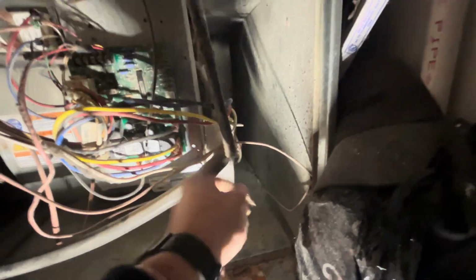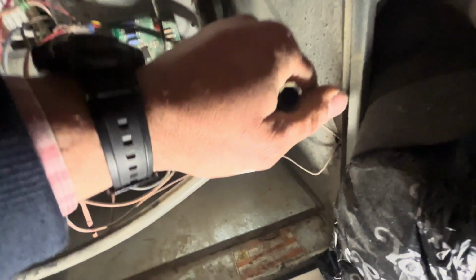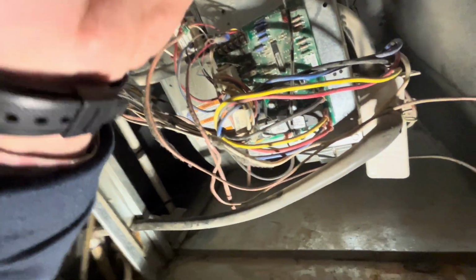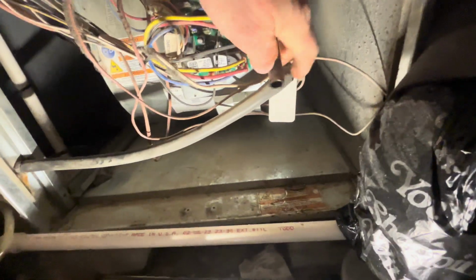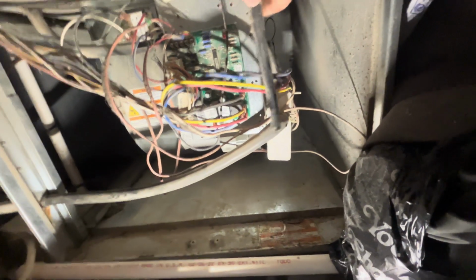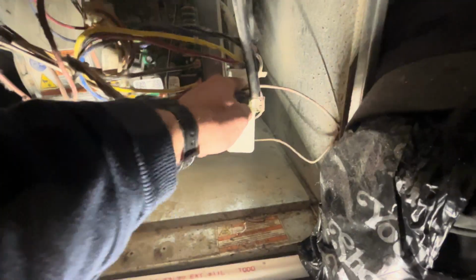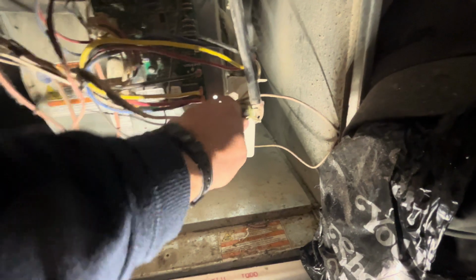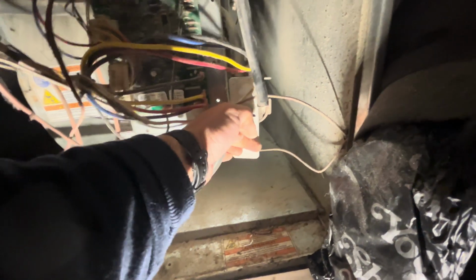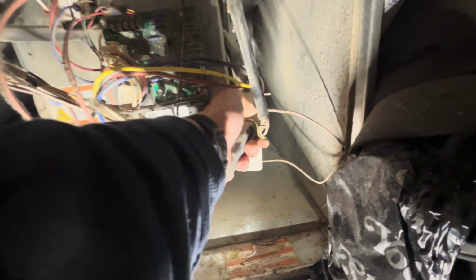That'll be a pressure switch problem. This trap is clogged too. Got that out, not supposed to do this, but watch. That's good, I don't like to, that's nasty water. Could break the trap by mistake, and I don't have a spare trap with me on a Saturday night.